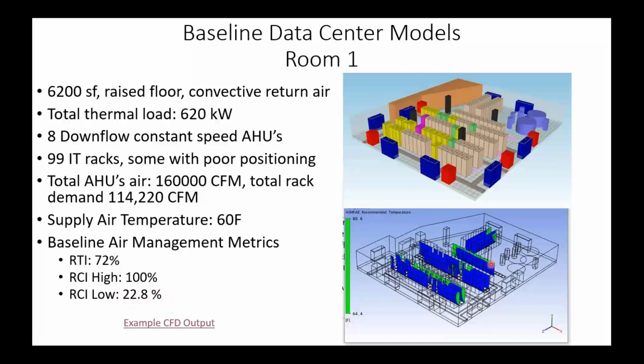This picture over here represents that. This is a conformance plot that comes out of CoolSim, and you see here that the temperature is 80.6 on the high side. This green is the conformance zone. That is to say that if you're green, you're good. It's kind of like a reference there, and blue means you're too cold. If you saw any red, it means you're too hot. These are rack inlet plots, and you can see we're seeing an awful lot of blue there, which means we're wasting energy.